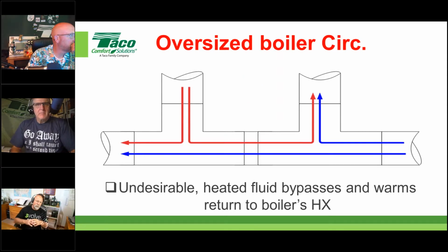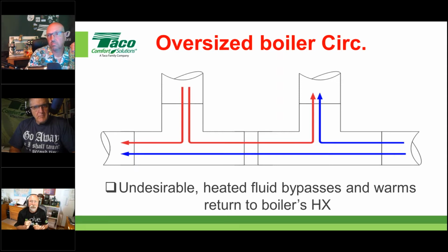You know, when we're not at design, unless you have a circulator that has a very wide range, and unless you have feedback coming from the boiler itself to vary the speed of the pump automatically, you're going to get a little bit of this. So there's no way around it with a fixed speed circulator. However, you could make it a lot better by following some of these tips that we're going to give you, okay?